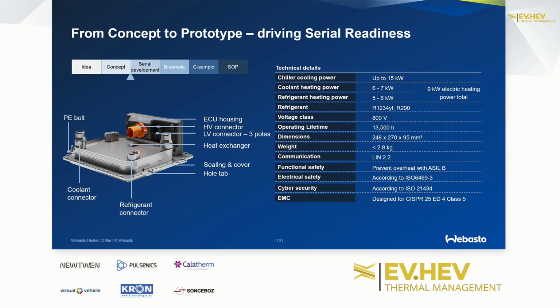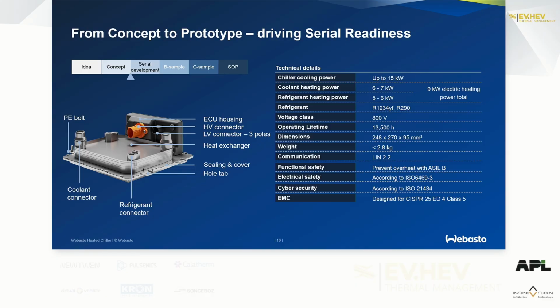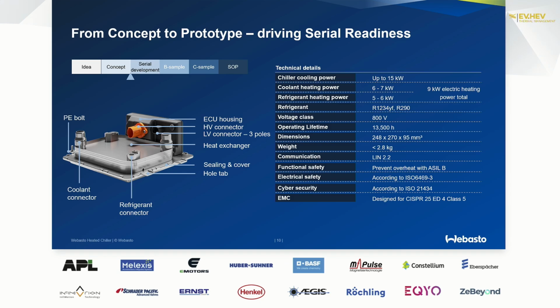The performance of the heated chiller is it has a cooling performance for the battery of 15 kilowatt, and it has some electric heating, so electric heat availability is 9 kilowatt, which we can distribute between coolant and refrigerant. And the capability of the single mediums is around 6 to 7 kilowatt for the coolant, and it's 5 to 6 kilowatt for the refrigerant.